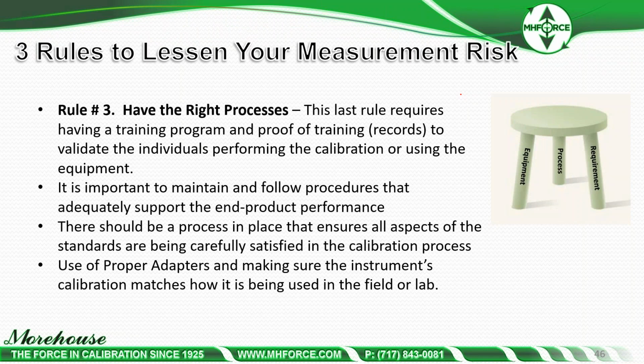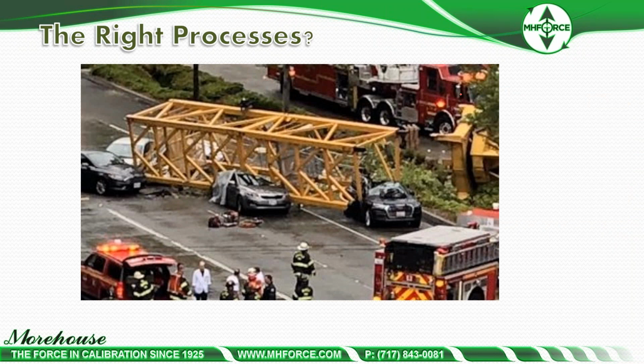So rule 3, have the right processes. The last rule requires having a training program and proof of training records to validate the individuals performing the calibration or using the equipment. Importantly, maintain and follow procedures that adequately support the end performance. There should be a process in place that ensures all aspects of standards are being carefully satisfied in the calibration process, with use of proper adapters, and making sure the instrument's calibration matches how it is being used in the field and in the lab. This picture, sad.